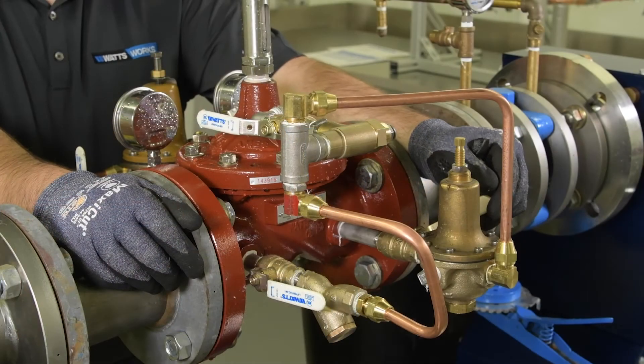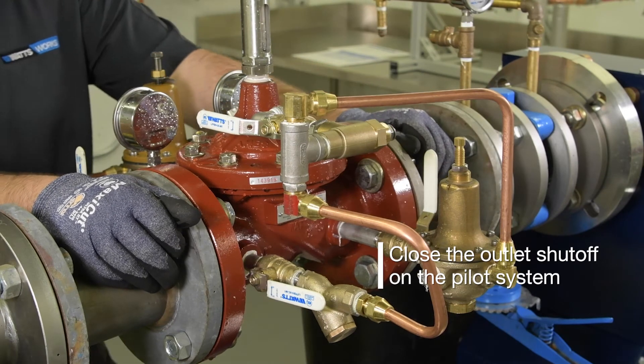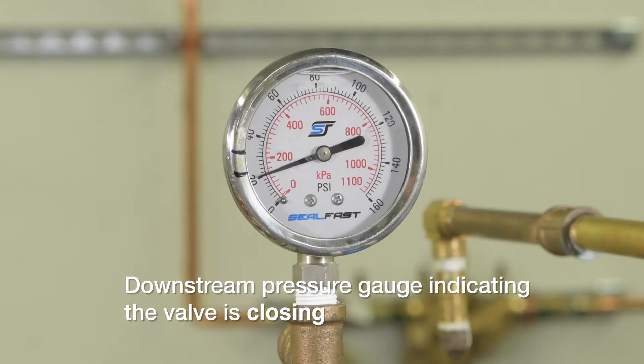To check that the valve will fully close, close the outlet shutoff on the pilot system, which will direct full water pressure onto the cover and should, if the valve is operating correctly, modulate the valve closed. Check your downstream gauge to confirm.